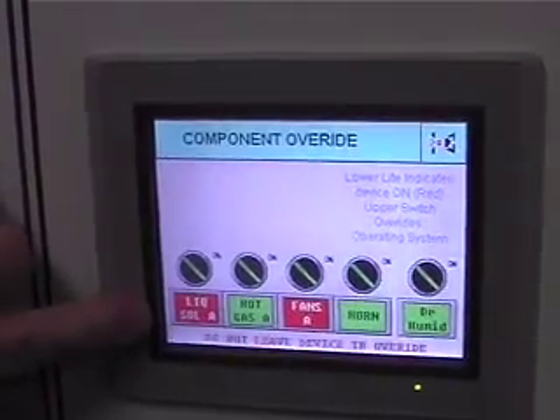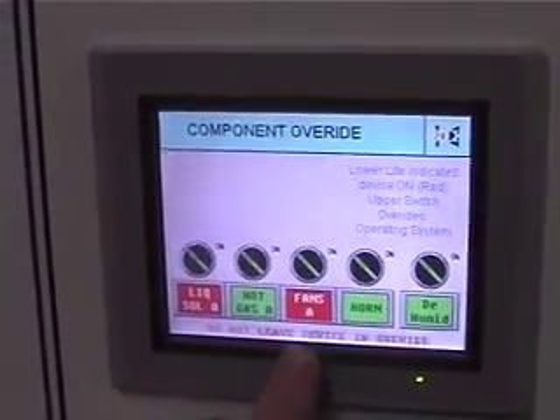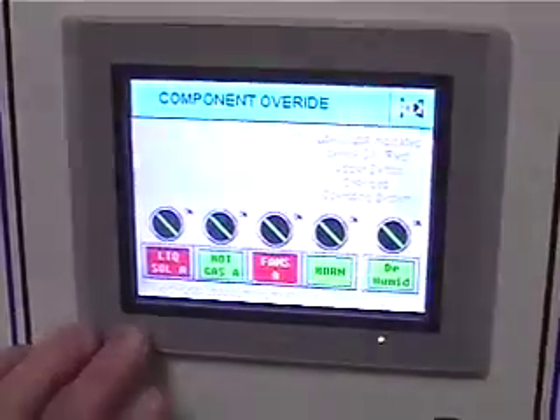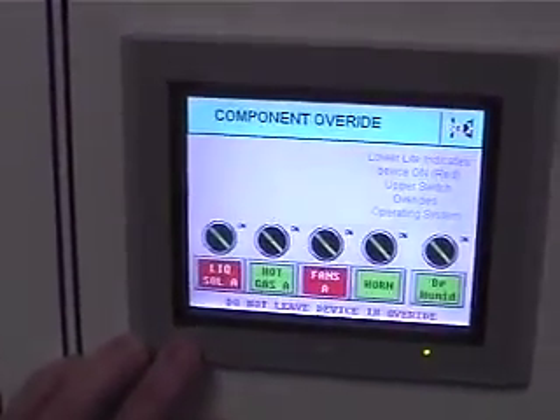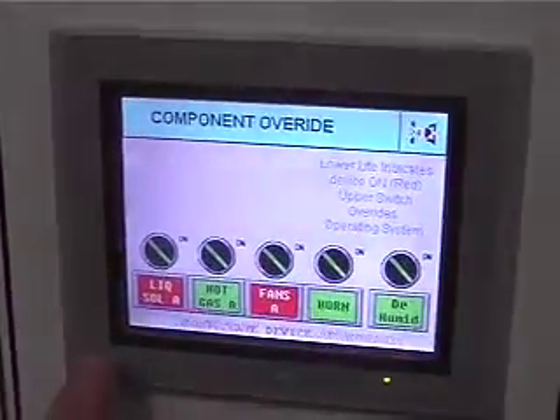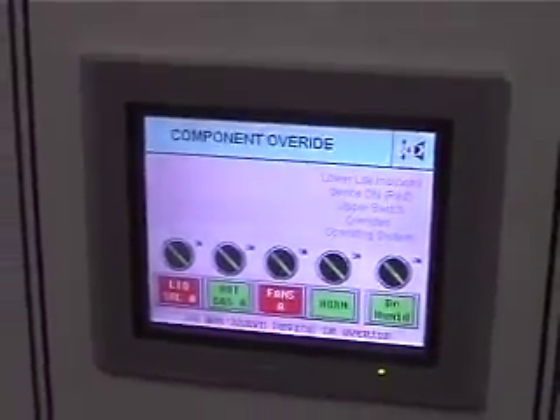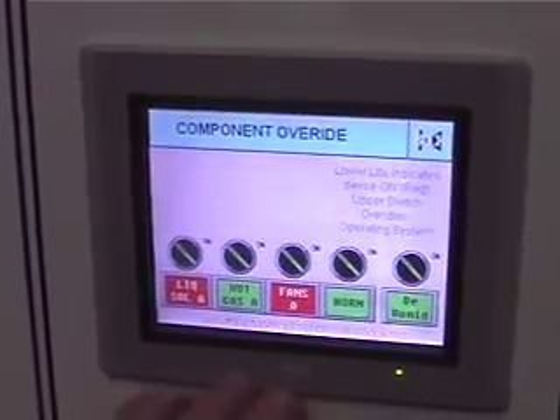What you can see is it's calling for the liquid line solenoid and the fans. In industrial speak, red is unsafe or on, rotating, hot, whatever. So we sort of use the same mentality here. If it's red, it means it's energized. If it's green, it's safe or it's off. These guys at the bottom just tell us whether or not the output at the PLC is sending a signal. So you can very quickly come in here and ascertain whether the PLC is the problem or it's something downstream if you're having a circuit issue.